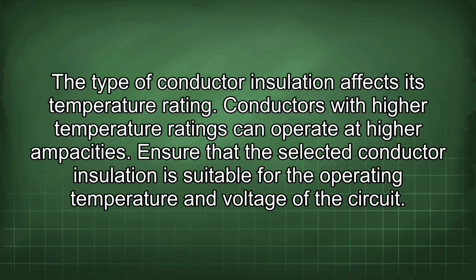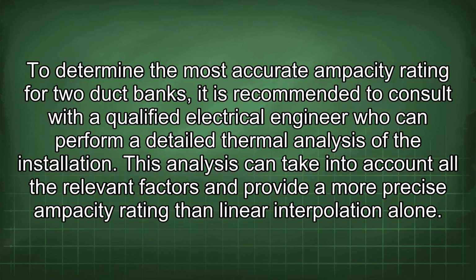Conductors with higher temperature ratings can operate at higher ampacities. Ensure that the selected conductor insulation is suitable for the operating temperature and voltage of the circuit. To determine the most accurate ampacity rating for two duct banks, it is recommended to consult with a qualified electrical engineer who can perform a detailed thermal analysis of the installation.